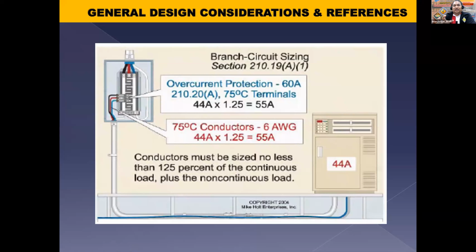Yung isang load kasi in a single outlet, predetermined na natin yung load amps niya na hindi siya aabot talaga doon beyond sa capacity ng circuit breaker natin or yung wire natin. So meaning to say, hindi talaga siya makakacause ng overload. So yung protection natin doon sa circuit breaker, more often than not, it will provide na lang yung short circuit at ground fault protection na ng load natin. Right? Just like in motor circuits, no?